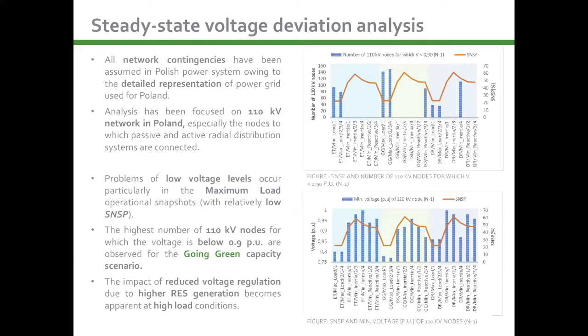Moving on to the load flow analysis results, preliminary analysis has demonstrated the absence of any issues relevant to steady-state voltage regulation for the transmission network. Therefore, our analysis has been mostly focused on the 110 kV distribution network in Poland. We have observed that problems of low voltage levels occur particularly in maximum load operational conditions. The impact of reduced voltage regulation due to higher renewable generation becomes apparent strictly at high load conditions. In general, the reactive power demand, both from load and the network sides, determines whether a voltage problem may occur in the power network.